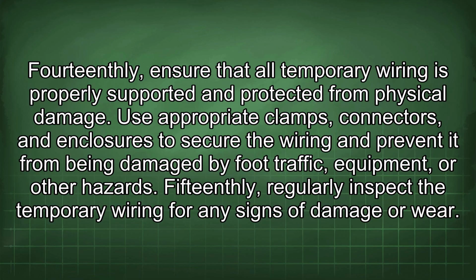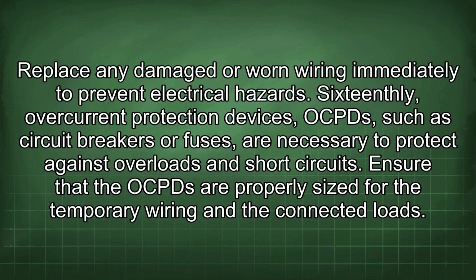14thly, ensure that all temporary wiring is properly supported and protected from physical damage. Use appropriate clamps, connectors, and enclosures to secure the wiring and prevent it from being damaged by foot traffic, equipment, or other hazards. 15thly, regularly inspect the temporary wiring for any signs of damage or wear. Replace any damaged or worn wiring immediately to prevent electrical hazards. 16thly, overcurrent protection devices (OCPDs), such as circuit breakers or fuses, are necessary to protect against overloads and short circuits. Ensure that the OCPDs are properly sized for the temporary wiring and the connected loads.